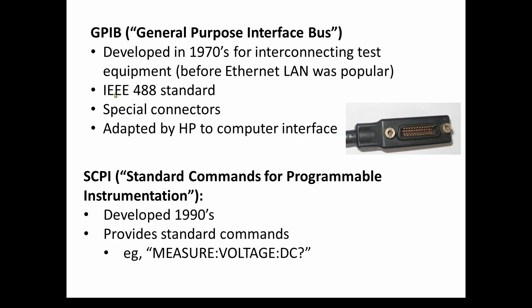The GPIB was defined in a standard called IEEE 488. IEEE means Institute for Electrical and Electronics Engineers. I've been an electrical engineer for over 45 years, and IEEE standards are extremely common in the electrical engineering world — this is just one. A bunch of engineers got together and defined this back in the 70s: what's a good standard interface connection between instrumentations? You can see here a hardware implementation of that standard — this is the GPIB connector, the IEEE 488 connector developed in this standard.